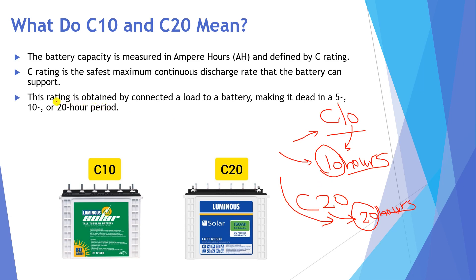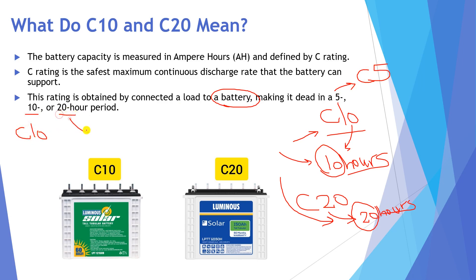This rating is obtained by connecting a load to the battery — C10, C20, C5, whatever — and making it fully discharge in 5, 10, or 20 hours. If a battery connected to a certain load goes dead in 5 hours, it is C5. If it goes dead in 10 hours, it is C10. If it goes dead in 20 hours, it is C20.